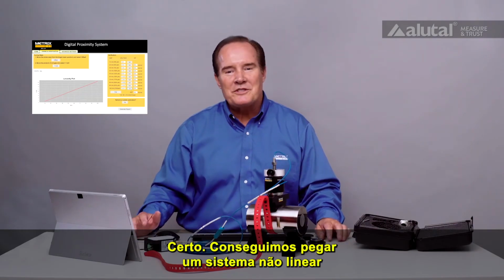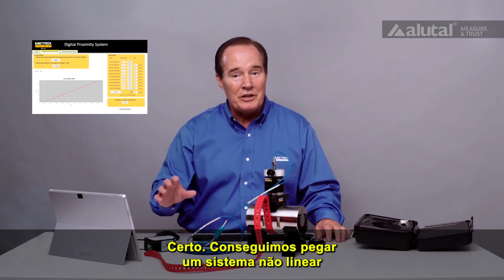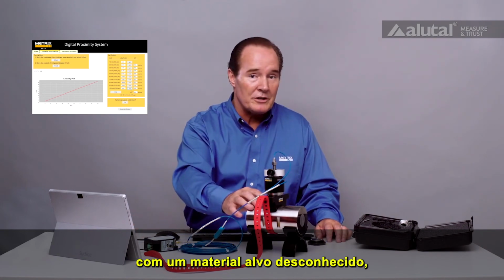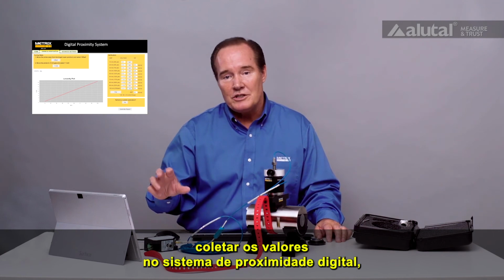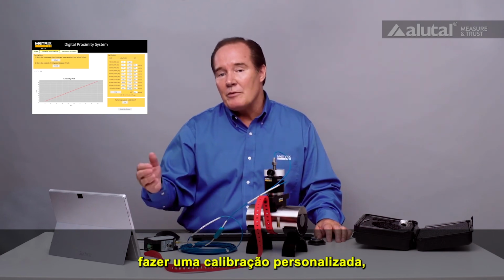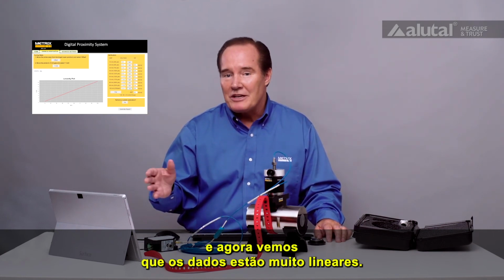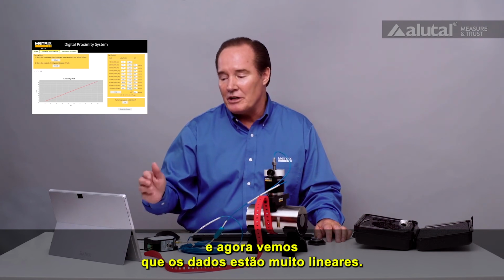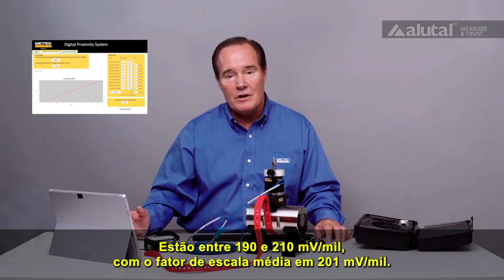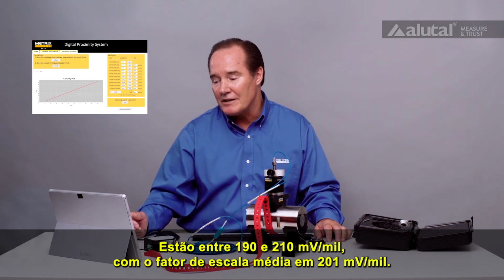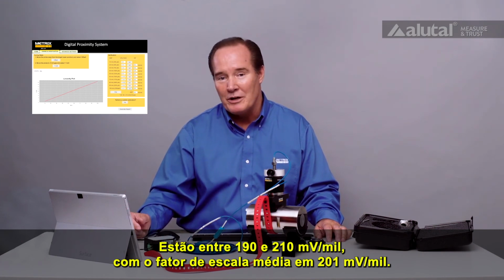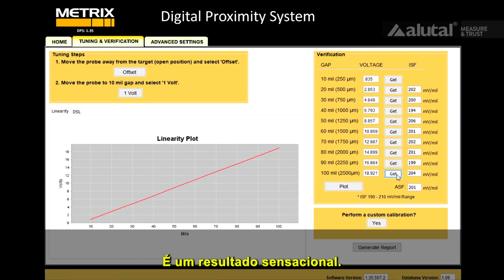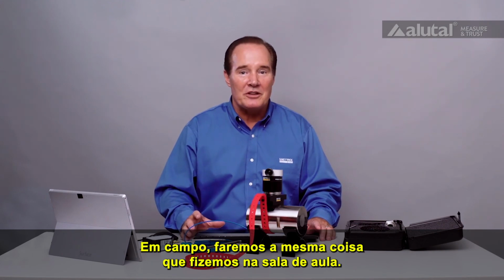All right, so we've been successful in taking a nonlinear system with an unknown target material, getting the values into the digital proximity system, then doing a custom calibration, and we can see now that the data is very linear. It's between 190 and 210, with the average scale factor being 201 millivolts per mil. Well, that's outstanding results.